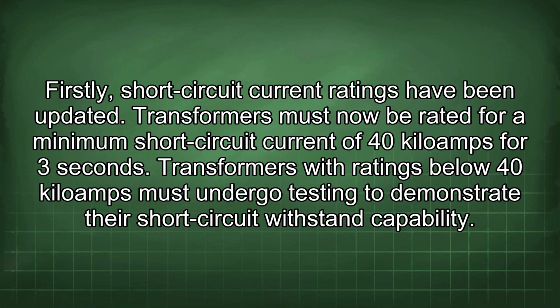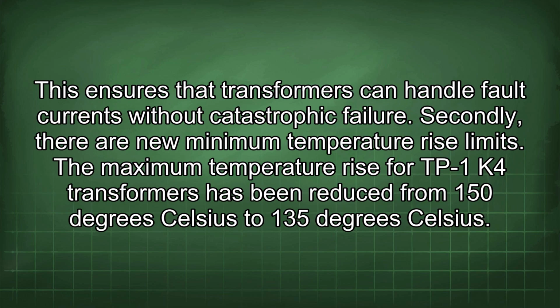Firstly, short-circuit current ratings have been updated. Transformers must now be rated for a minimum short-circuit current of 40 kA for 3 seconds. Transformers with ratings below 40 kA must undergo testing to demonstrate their short-circuit withstand capability. This ensures that transformers can handle fault currents without catastrophic failure.